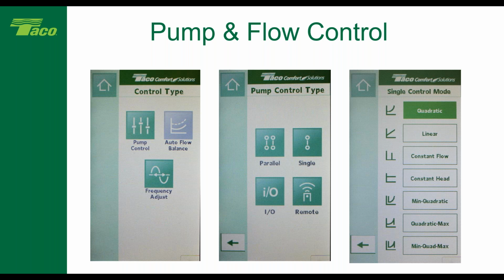And minimum quadratic is you define a predefined minimum speed. So if you're doing like variable primary, chilled water plant, and you know what your minimum flow has to be, you can program in that minimum flow and that pump will come down to that minimum speed and it's not going to go any slower. Okay. Same with min max. If I know what my defined max is, I can set that min max and the pump will operate between those two upper and lower limits.